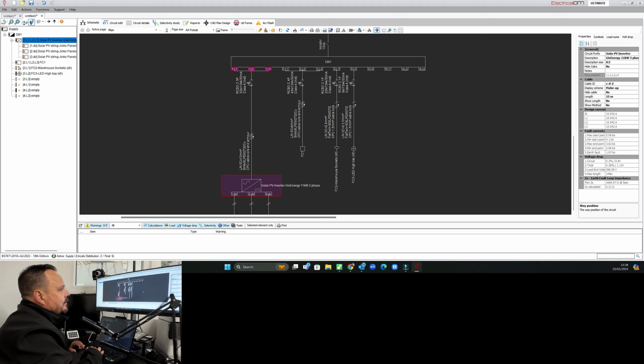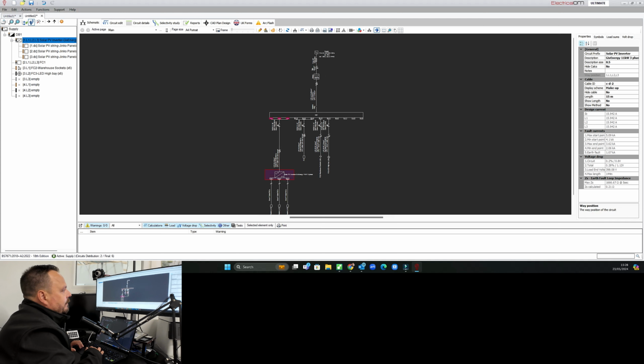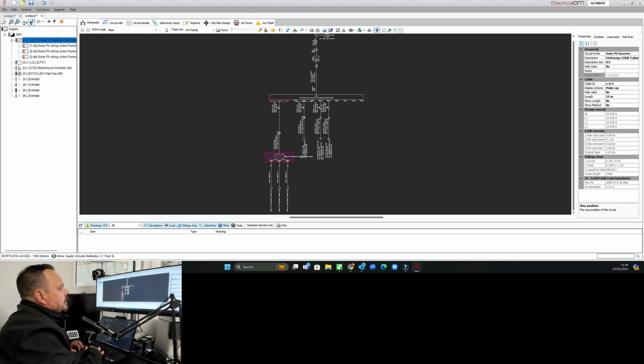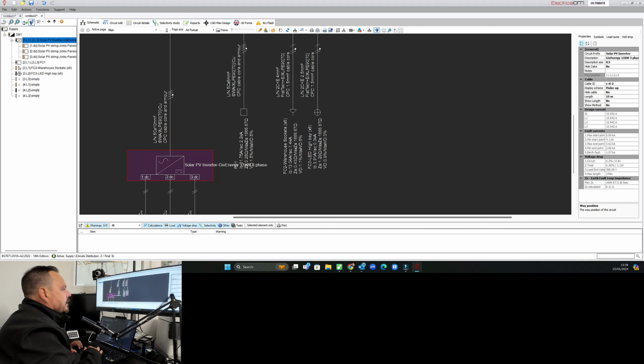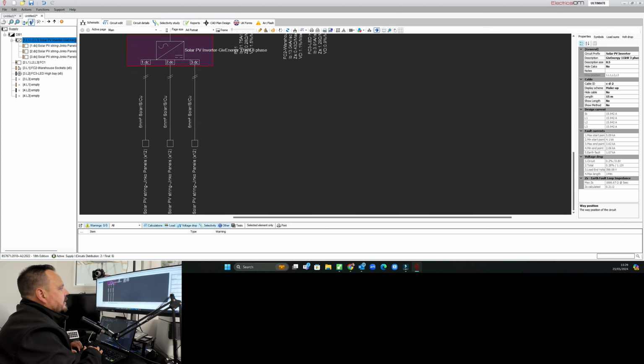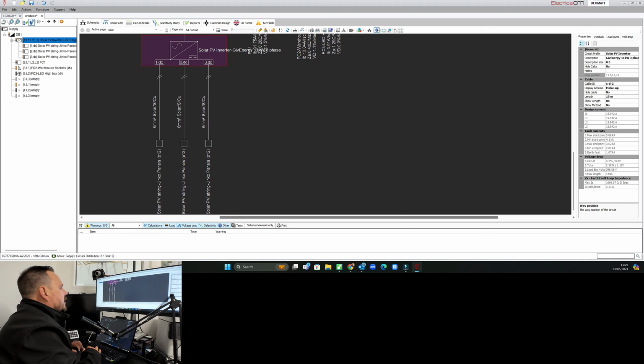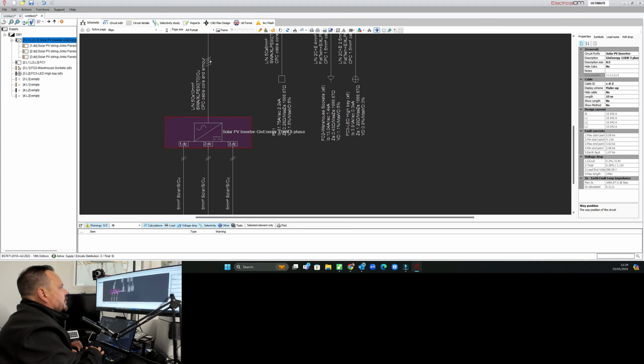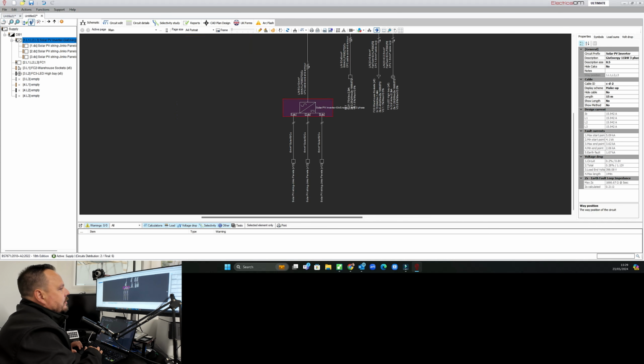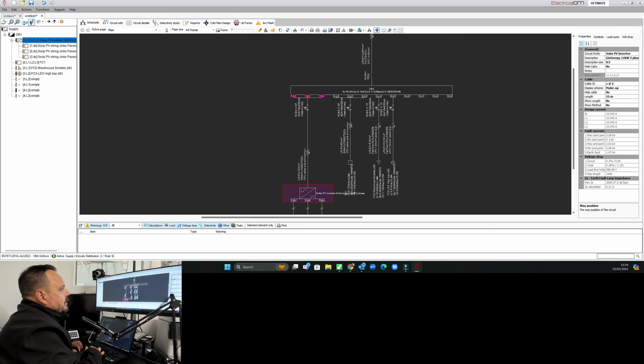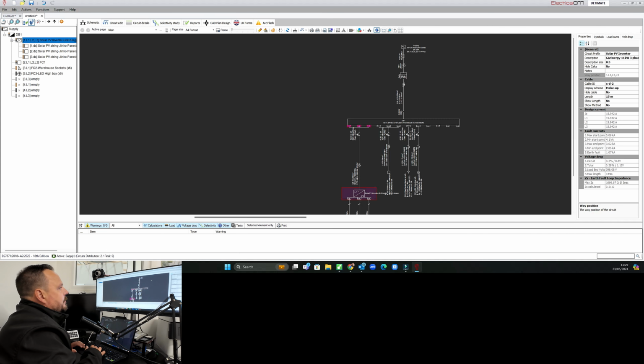So if we go back to the schematic now, you can see we've got our 3 strings on the inverter. It's 11 kilowatt. We've got our final circuits for the socket. If we want, we can show the calculations within the circuits. So if we click that on here, show circuit calcs, it'll tell us what all of those things are. If we zoom in at the end, what the expected ZS's are, and your fault currents that you may find within those circuits. So that's super useful. And the same on the solar side as well, it'll pop all that information in at an inverter level. So if you want to know what your anticipated calculations are, they can all be shown within this picture form.